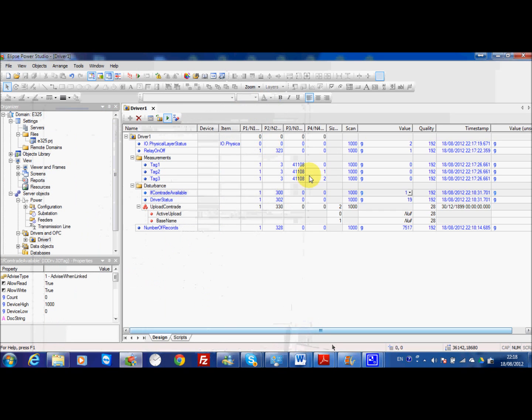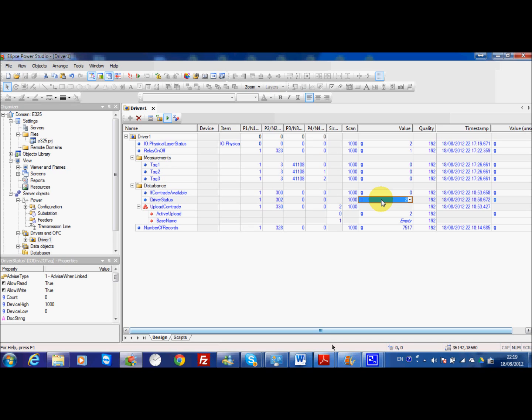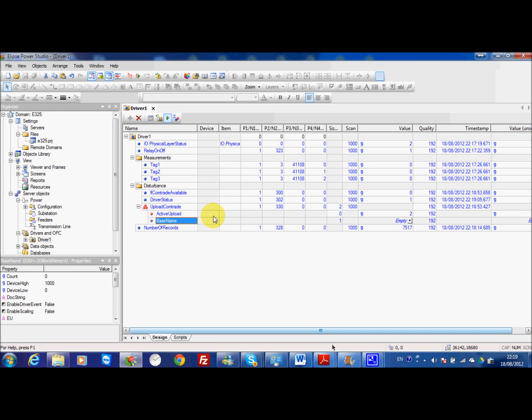So here the value is 19. 19 means waiting records. If I want to trigger upload here I need to write 2 and then it's ready and transferred. Then these two files come back to normal interrogation. I can specify the base name if I want to change the comtrade file name to my computer.